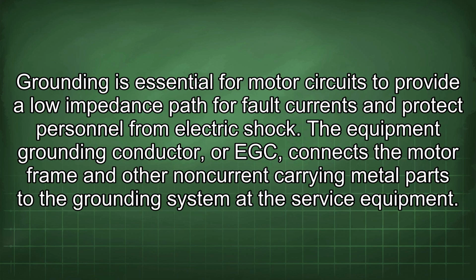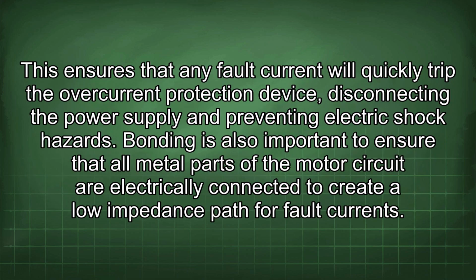Grounding is essential for motor circuits to provide a low impedance path for fault currents and protect personnel from electric shock. The equipment grounding conductor, or EGC, connects the motor frame and other non-current carrying metal parts to the grounding system at the service equipment.